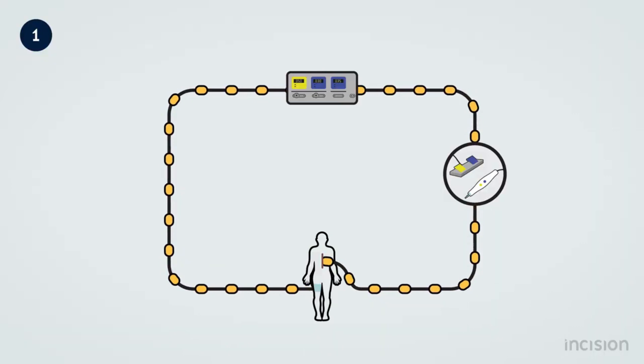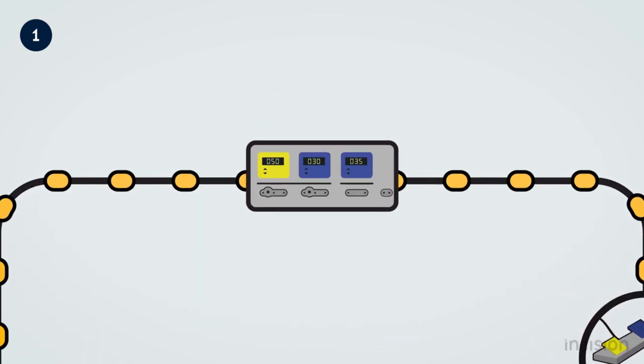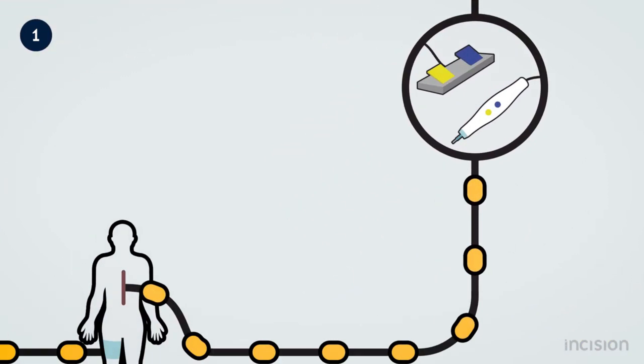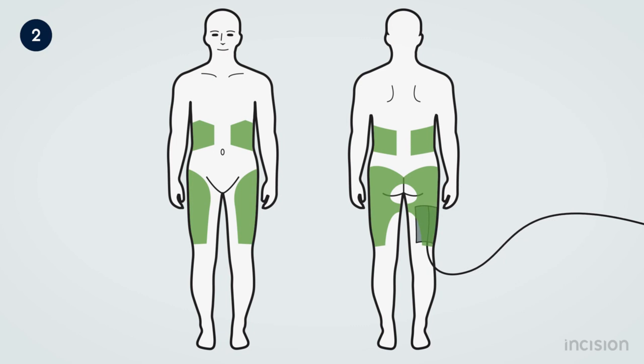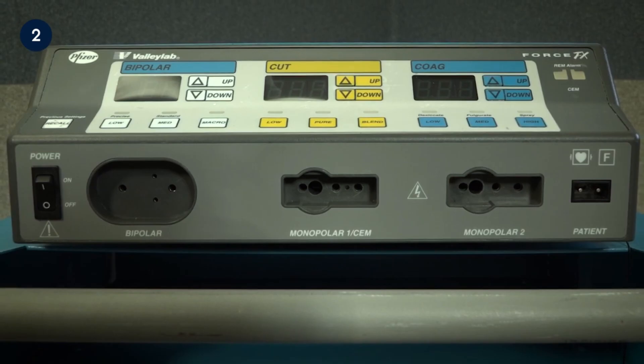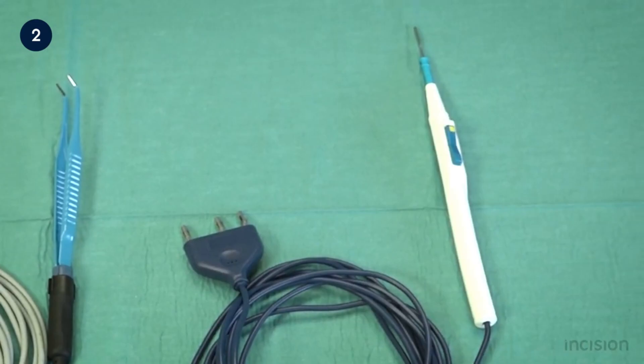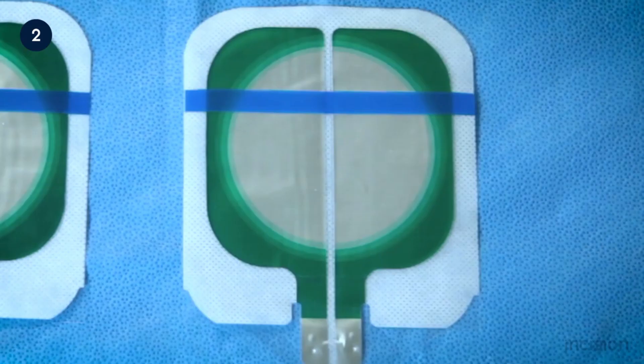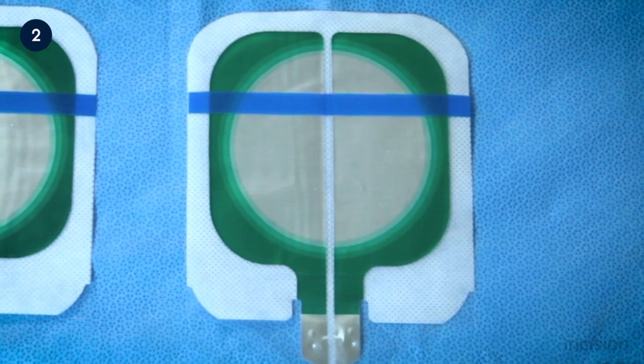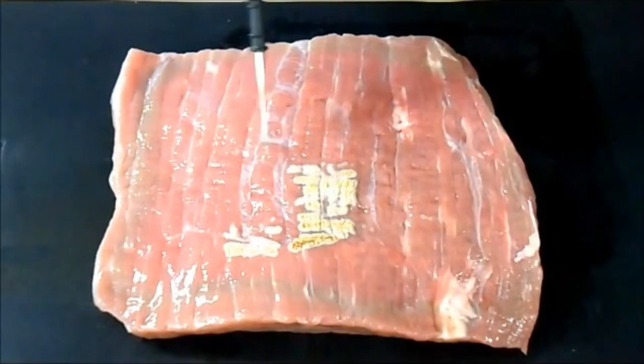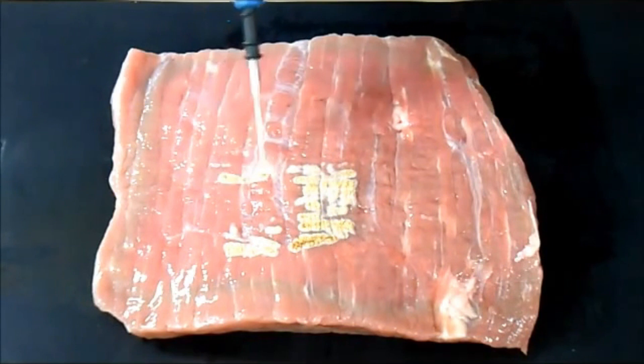Electrical current flows when electrons from one atom move to an adjacent atom through a circuit. Heat is produced when electrons encounter resistance. For current to flow, a continuous circuit is needed. In the operating room, the circuit is composed of the patient, the electrosurgical generator, the active electrode, and the return electrodes. The electrosurgical unit is the source of the voltage. Electrical energy is converted to heat in tissue as the tissue resists the flow of current from the electrode.